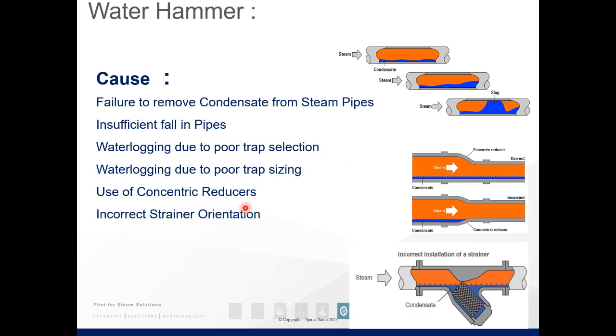Looking at these images, I'll explain the images first. If you have a steam line that has condensate in it, as the steam passes over the surface of the condensate, there is a friction transfer that slowly picks up speed in your condensate. The second image is a middle point between the slug, the water hammer you see, and the initial stages of condensate pickup. As that friction builds up, the speed builds up and it creates a larger wave in your system, until you get to the point where you have a slug or a blockage of condensate in your steam pipe, with the steam behind it propelling this slug down your system.